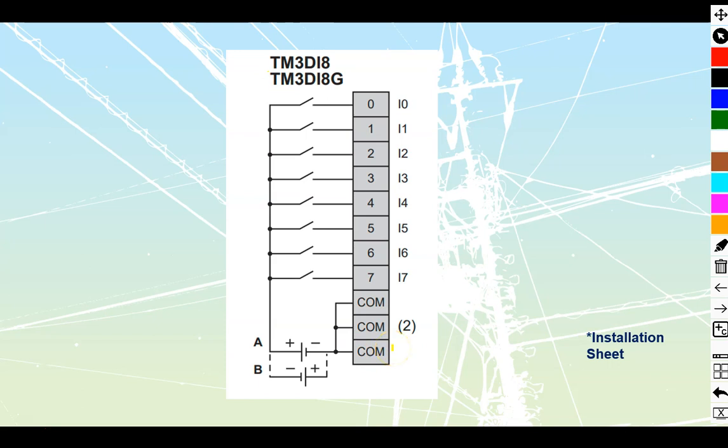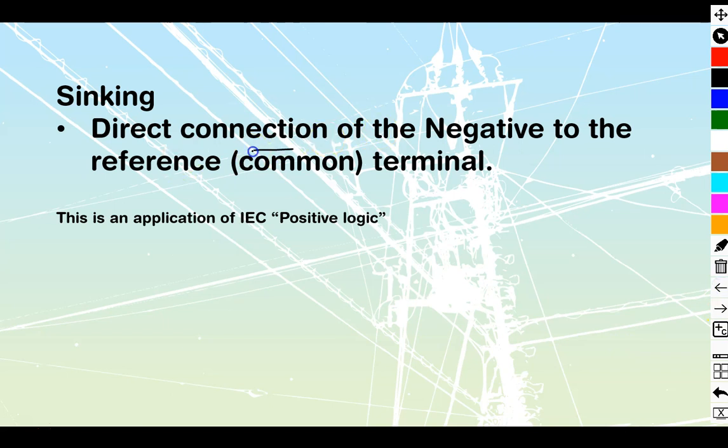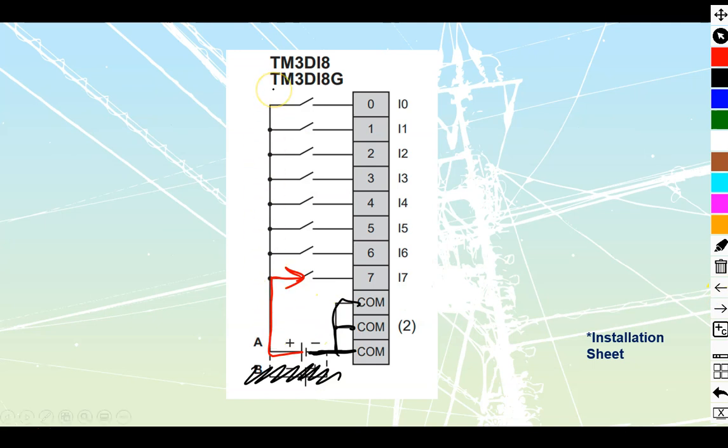It shows me that I can do one of two things. I can either attach a negative that they have over here to my commons like this over here and then take a positive stinger out to my field devices to switch in. Or I could do the alternate, the B method over here. What you're not supposed to do is A and B at the same time. B is going to be a sourcing input. We're going to scratch that out because that's not what we're looking at. This is what we're going to replicate. Taking a negative 24 volts DC because that's what it's rated for. We're attaching the negative to the common because that is going to be sinking - direct connection of the negative to the reference or to the common that we will have. And then taking our positive out to the field devices.